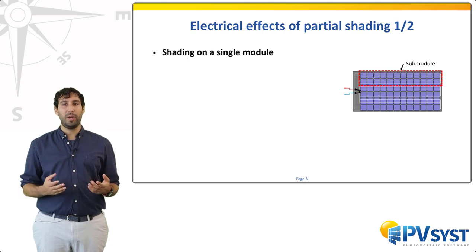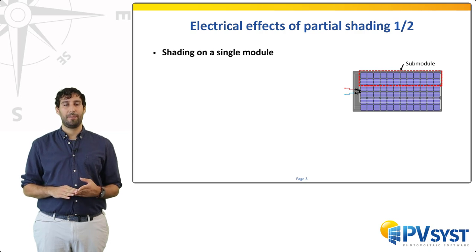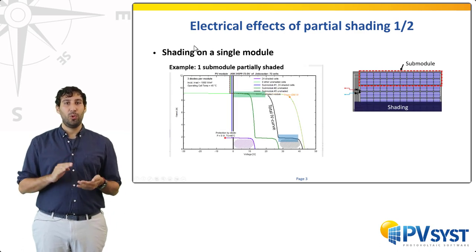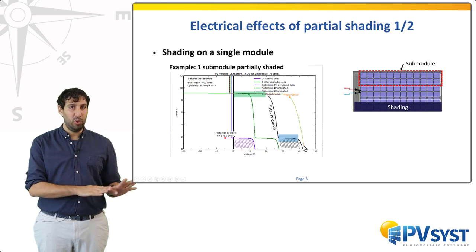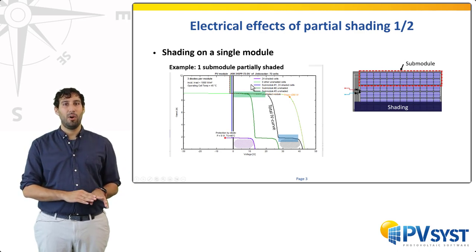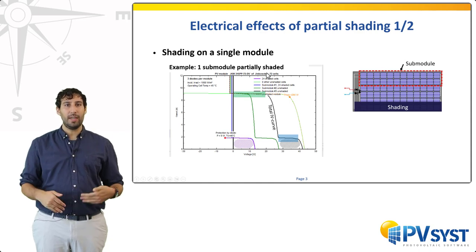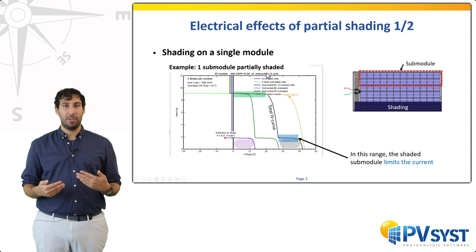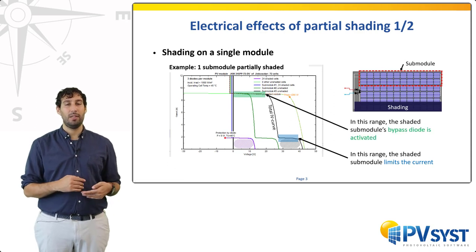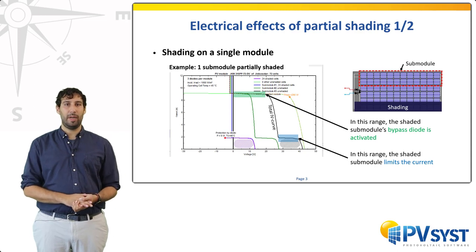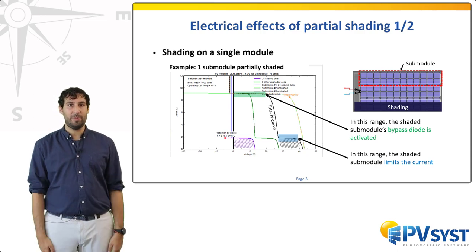When the submodules forming the module are put together, you obtain the total IV curve in black. Here we have shaded one submodule among the three. There are two operating regimes, shown in blue and green: either in blue at a current limited by the shaded cells, or in green at a lower voltage because the bypass diode is activated. In the second regime, the power from the diffuse irradiance shining on the shaded submodules is lost. This roughly corresponds to the dashed area. This is the first type of mismatch loss.